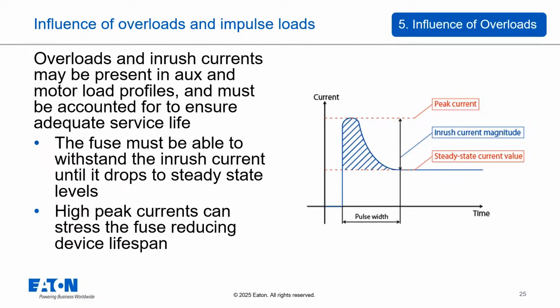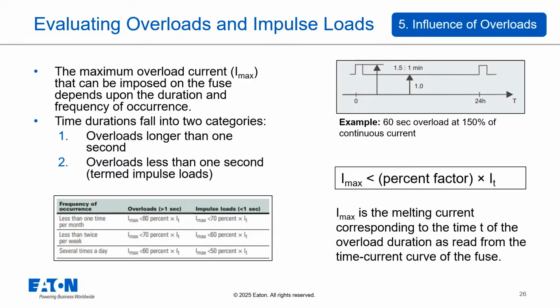We typically categorize overload time durations into two groups, those longer than 1 second and shorter than 1 second, which we call impulse loads. To evaluate if a fuse can handle overloads, we look at its time current curve and apply a percent factor. The maximum overload current, Imax, the fuse can withstand for a given duration, T, is typically less than the actual melting current, I sub T, shown on the time current curve for that duration. This accounts for cycling stress and other factors.